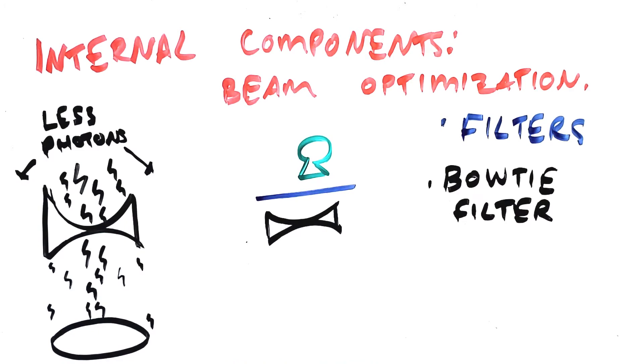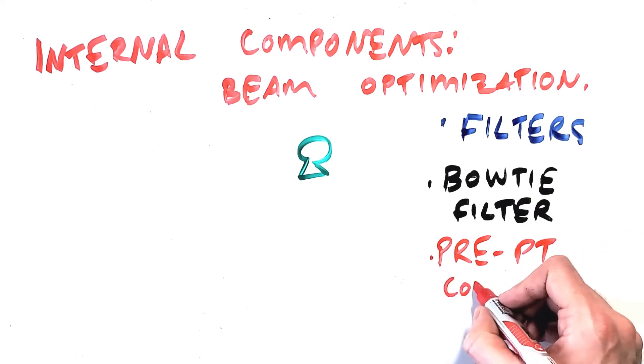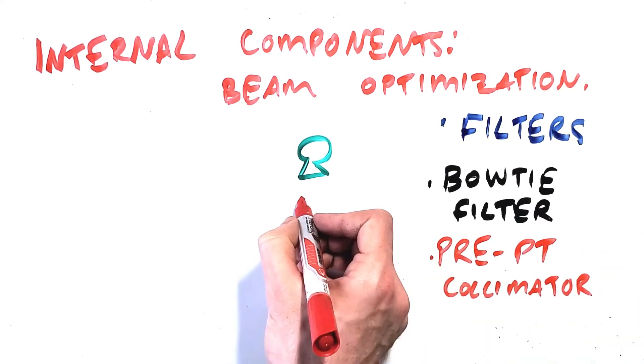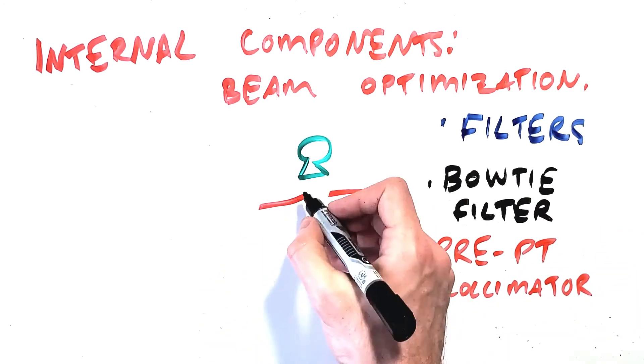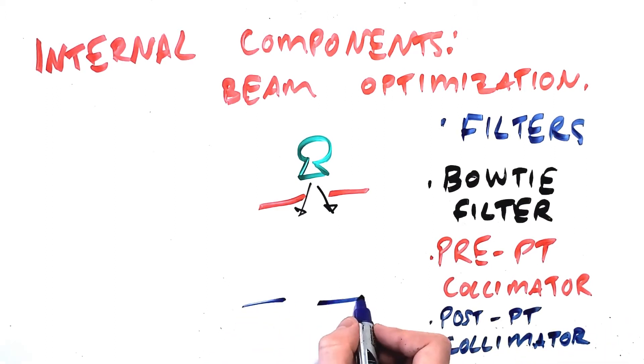As in conventional x-ray there is a collimator between the tube and the patient which shapes and defines the edges of the x-ray beam leaving the tube. And unlike conventional x-ray there's also a post-patient or pre-detector collimator which aligns to the edges of the detector area being used. Again shaping the beam before it hits the detector and absorbing scatter radiation to improve image quality.